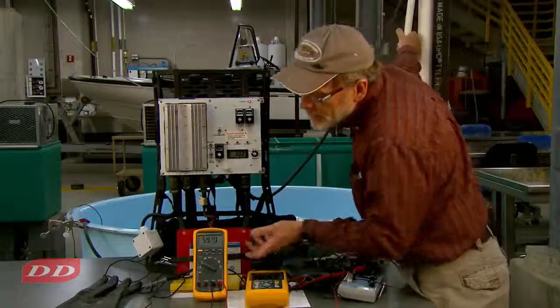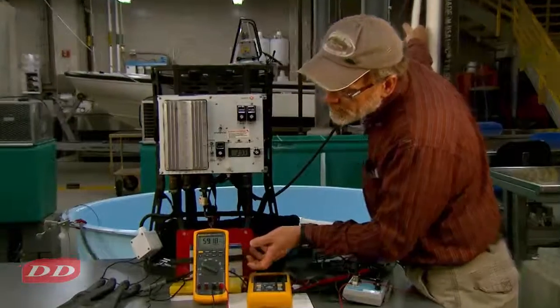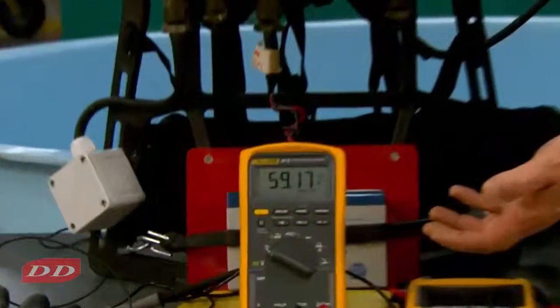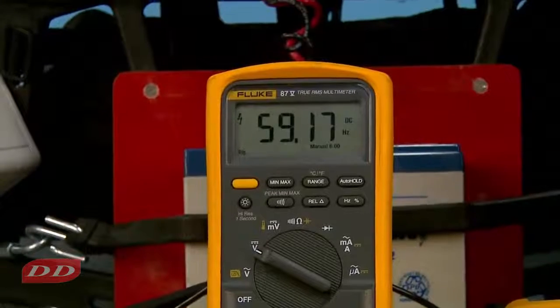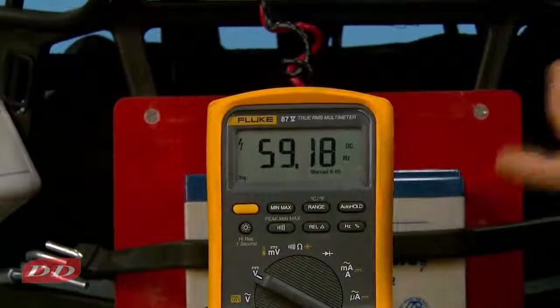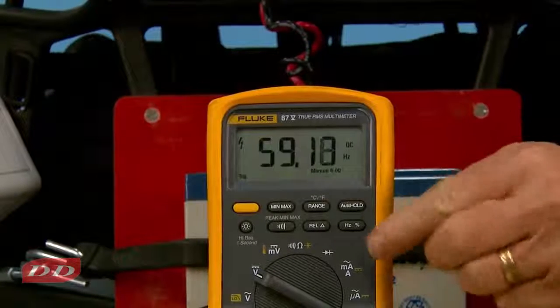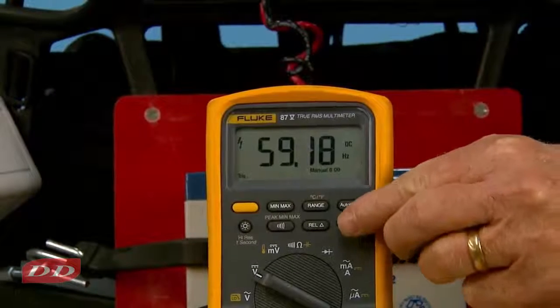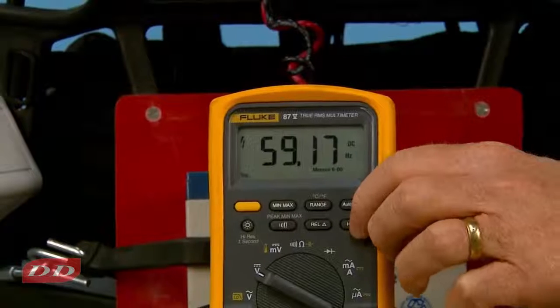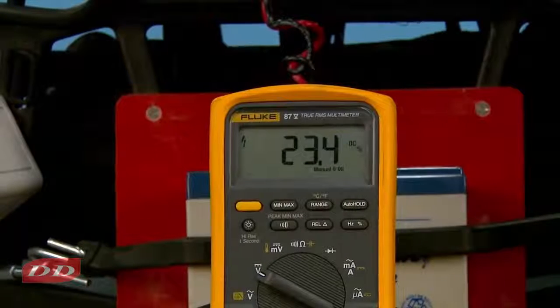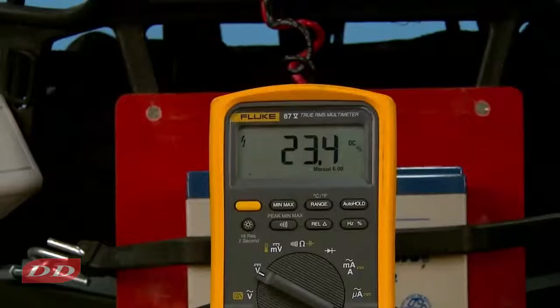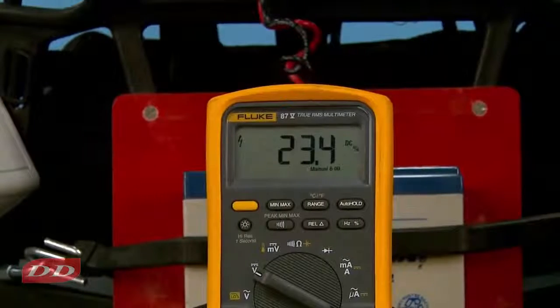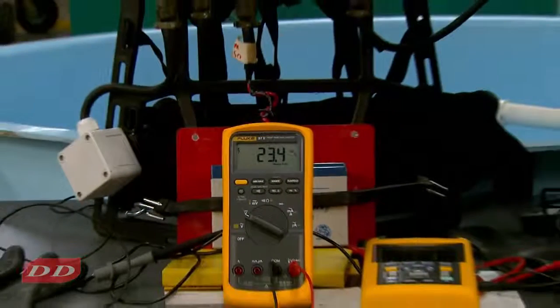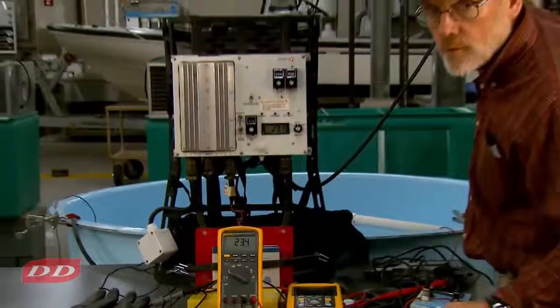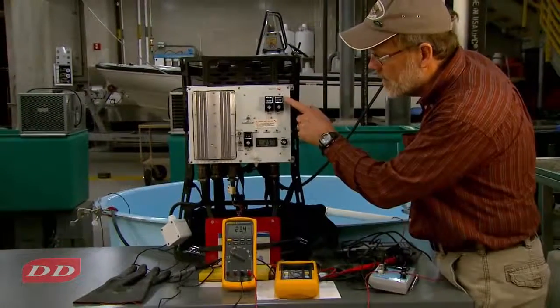So now there's the Hertz, nearly 60, about 59 pulses per second, or Hertz, which corresponds quite nicely with our setting of 60. I'll hit the Hertz duty cycle button once, and that should give us a duty cycle reading, it looks like, of just over 23%, and that corresponds again quite nicely with our 24% duty cycle setting here.